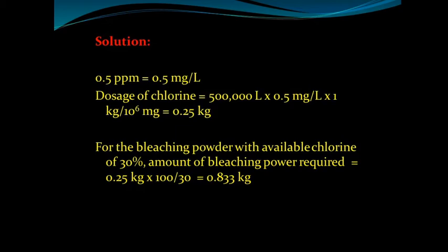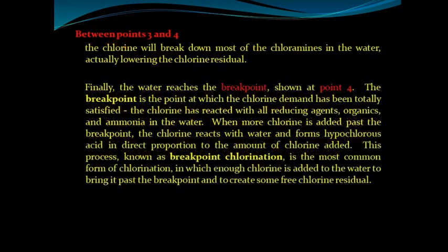Okay, so this is about the method of disinfection and breakpoint of chlorination. Breakpoint is nothing but a point in the chlorine dose residual curve at which all the destructible chloramines and also the chloro-organic compounds are decomposed and the free residual chlorine begins to appear.